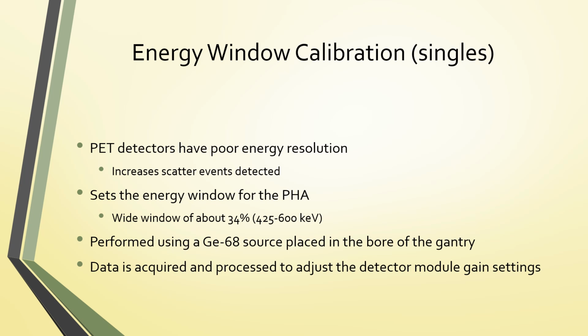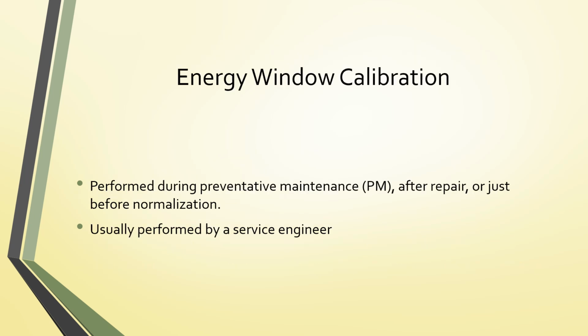The energy window calibration does set the energy window for the pulse height analyzer, and it's performed using a germanium-68 source that's placed in the bore of the gantry. Data is acquired and processed to adjust the detector module gain settings. The energy window calibration is performed during preventative maintenance, after repair, or just before a normalization study. This is usually performed by a field service engineer. So it's not typically something that a technologist is a part of or performs on their own.